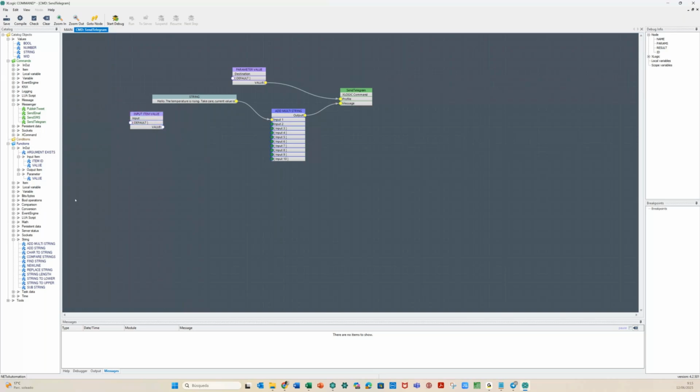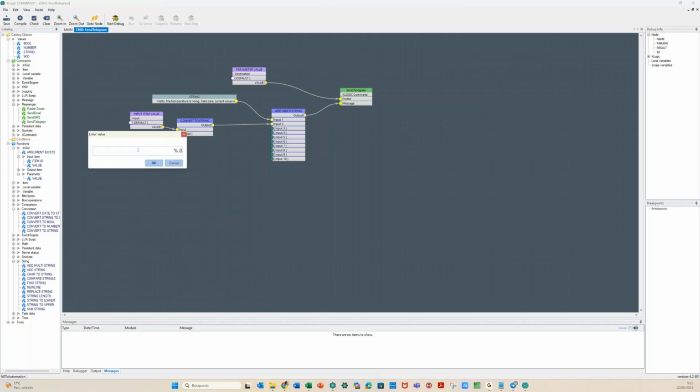So let me do the conversion. Use convert to a string this value. So I can convert to string. It could be a text included here, because if not, the BMS will do the conversion, but without format. So maybe with 10 decimals. So I can put a format here, no decimals or 2 decimals. So this is just to know what the format is to include this.